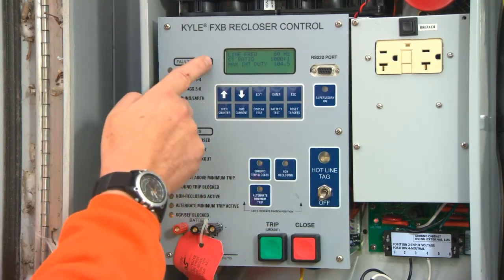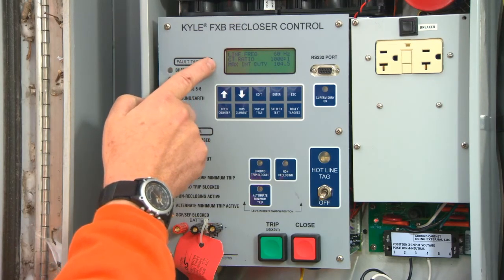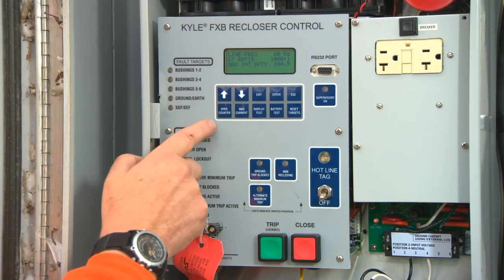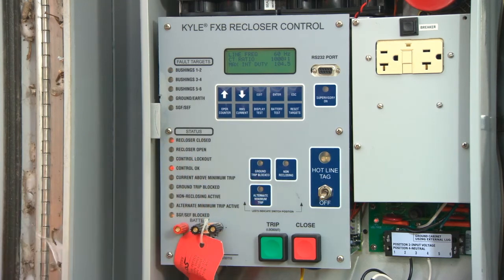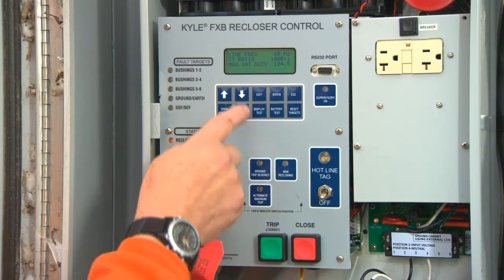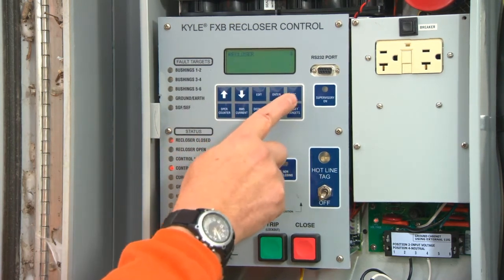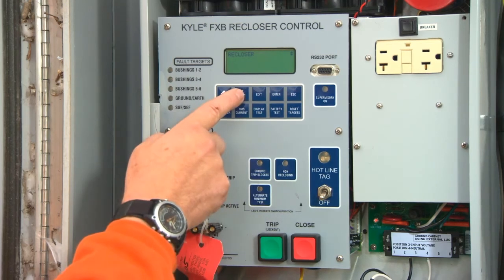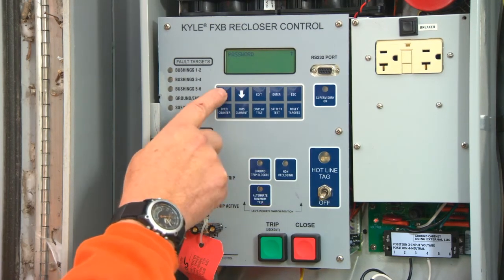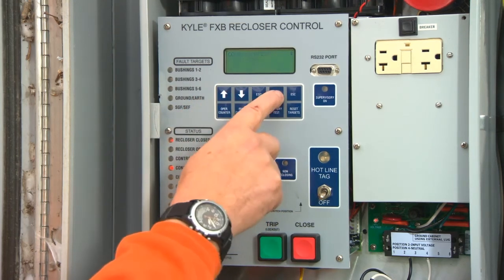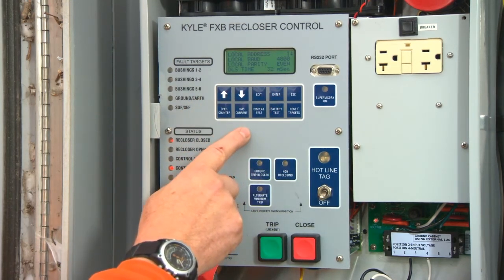The screen will now display line frequency, CT ratio, and interrupter duty. This latter number is a calculation that will tell you the percentage of wear on your contacts. The control does this calculation for you. Press Escape. Use the down arrow to select Communications and press Enter. This will display an address and baud rate, which is only used for communicating remotely to this unit.